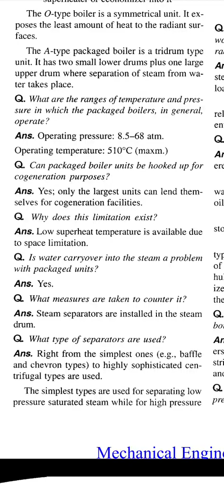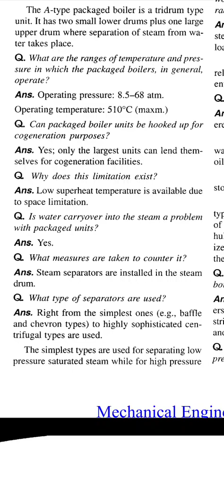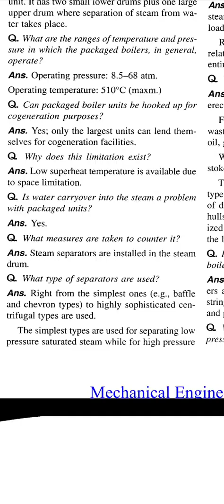Question: is water carryover into the steam a problem with packaged units? Yes. What measures are taken to counter it? Steam separators are installed in the steam drum. Question: what types of separators are used? Answer: right from the simplest ones, baffle and chevron types, to highly sophisticated centrifugal types are used.